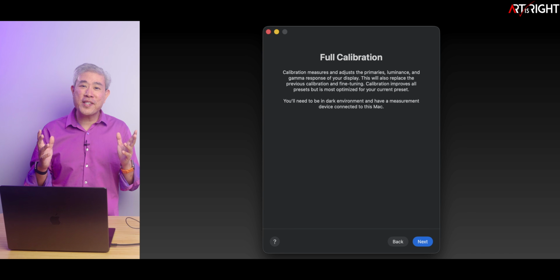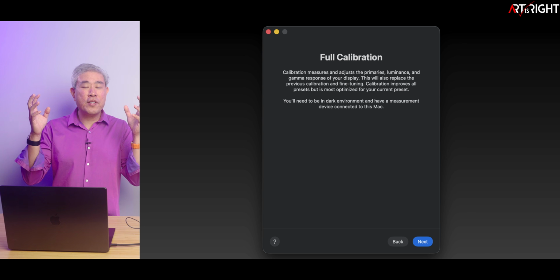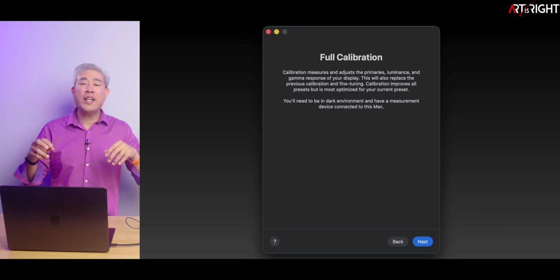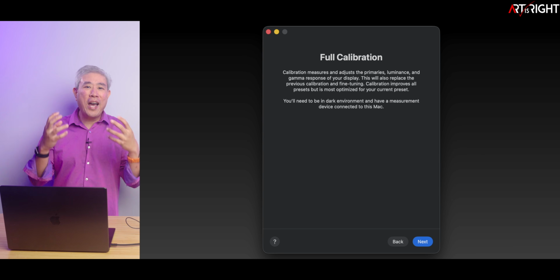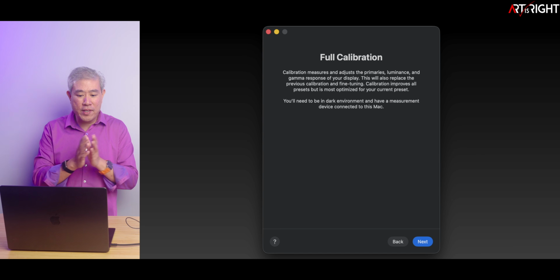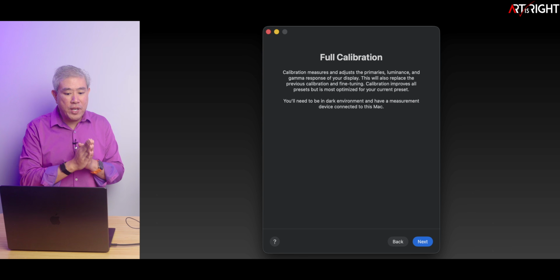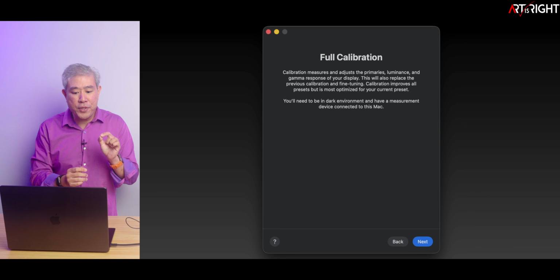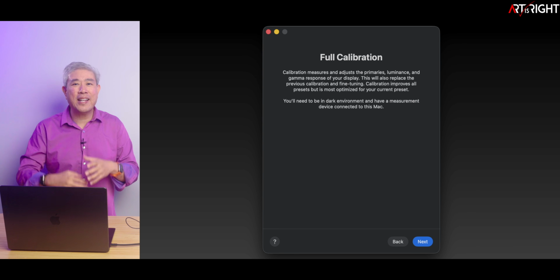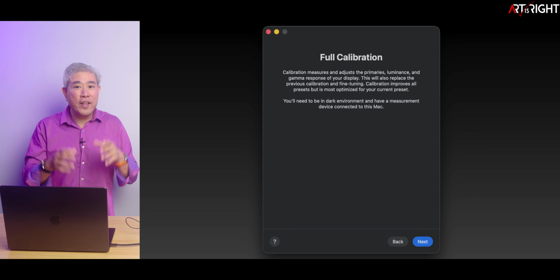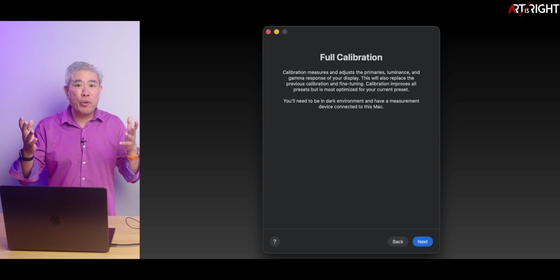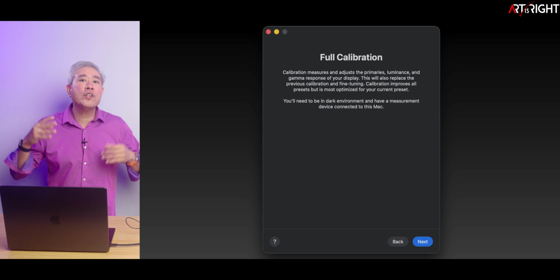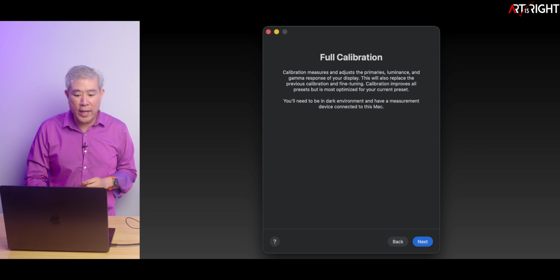This is the part where I was saying the best thing to do is to create a preset, do a fine tune, and just leave it. And afterwards, a while down the road, you can come in and do the full calibration, to which once you do the full calibration, you have to go back and do the fine tune again. So that's just something to think about there. Calibration improves all the presets, but is most important to optimize for your current preset. That is the one that you're going to use the most. If you have created a custom one following my guide, that's most likely going to be your primary preset. So you want to choose that first before you go and do the full calibration.